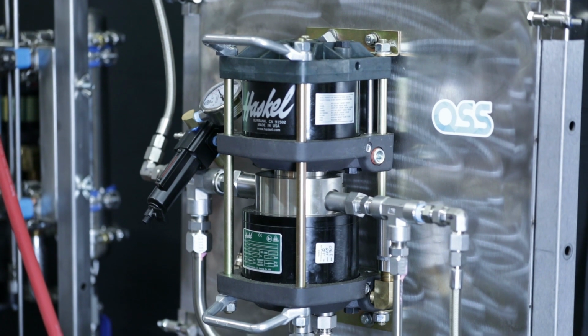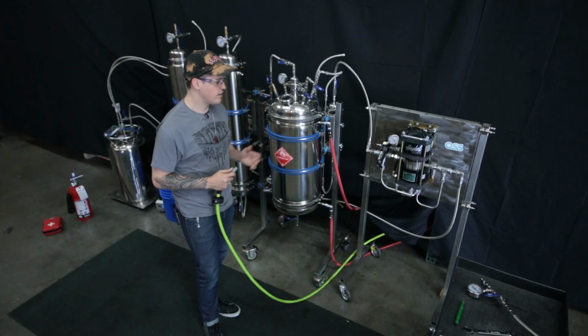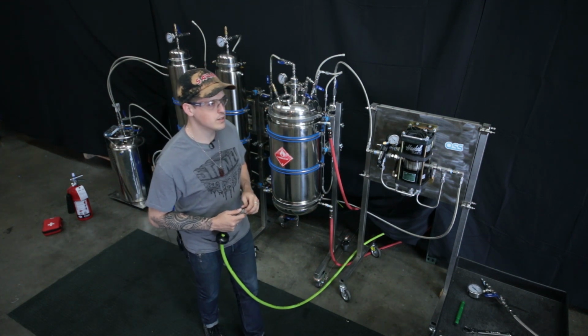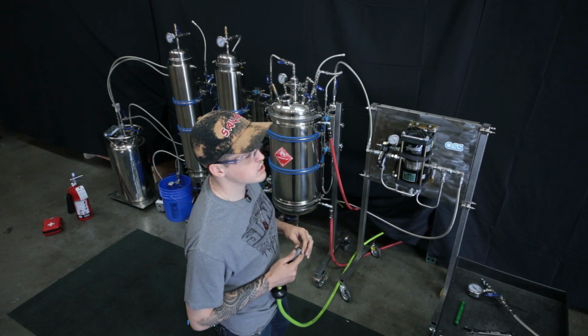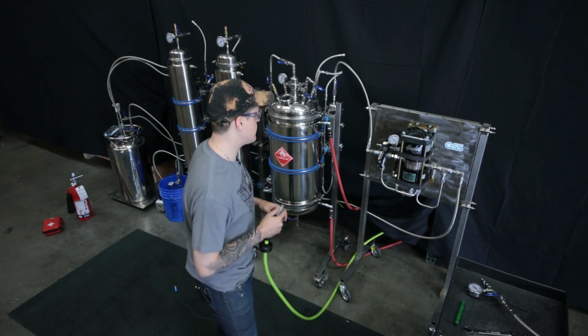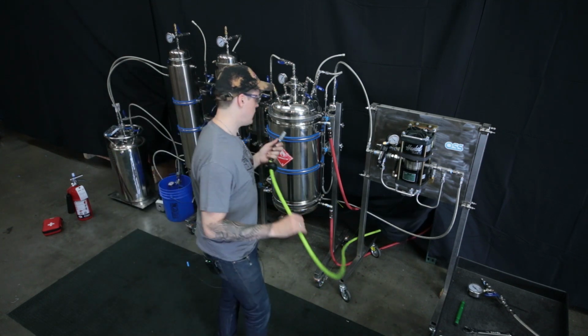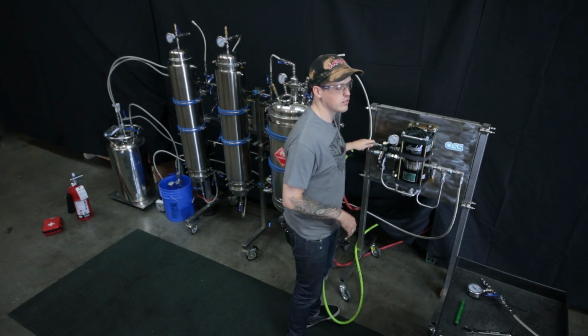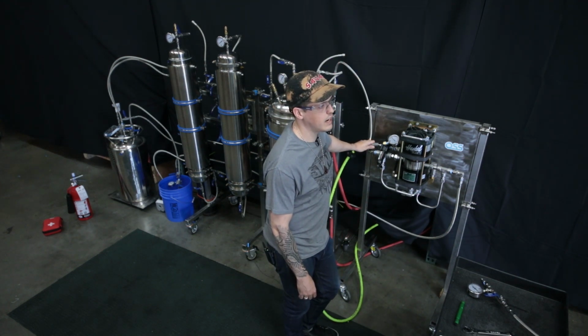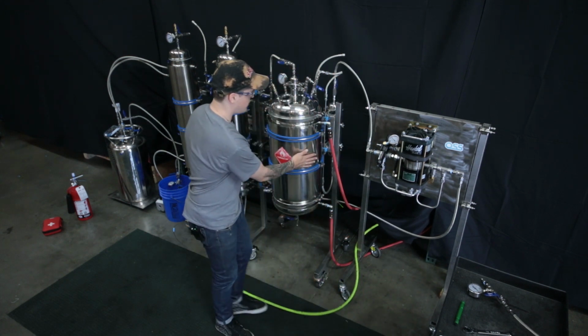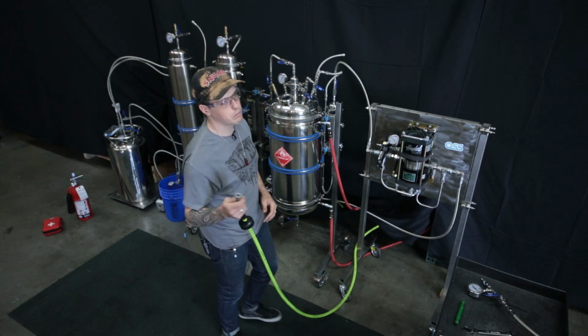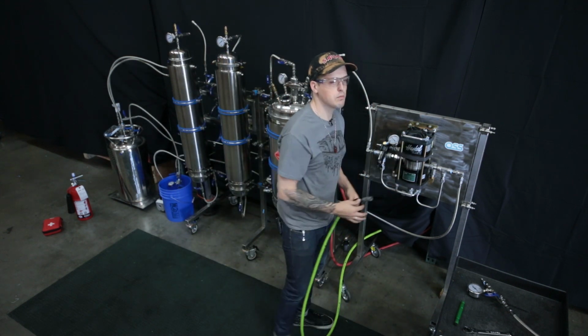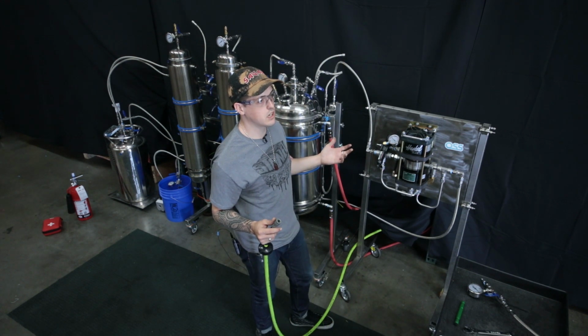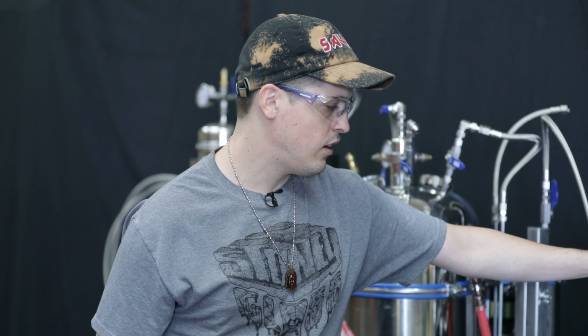Today we're using a prototype Haskel pump, provided to us by them directly, and we've been testing it out for a while now. We're getting good performance out of it. Right now we're seeing about 1.12 pounds per minute on the recovery side of things, at about 120 degrees Fahrenheit evaporation temperature on the evaporation pot. Somebody can quote that in the comments on a Celsius conversion. It's a really great pump. It's beaten out a couple TRS-21s, maybe 3 or 4 of them in one. This pump is definitely more than the original EXT420 Haskel. Just look at the size of this thing, it's extremely beefy.